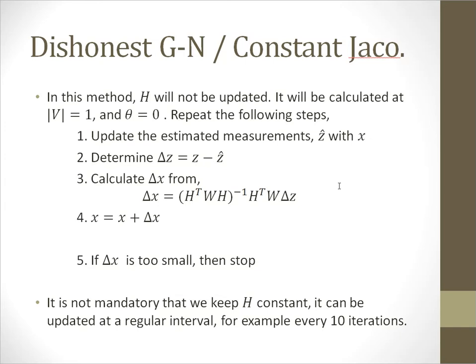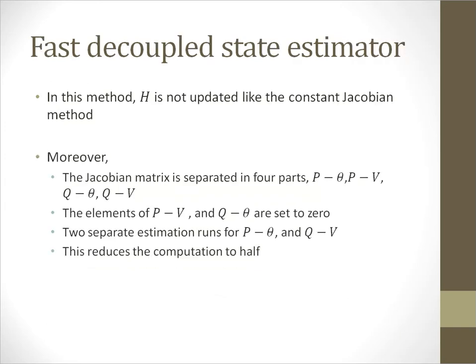In the fast decoupled state estimator, like the constant Jacobian method, H will not be updated. Moreover, we are going to separate the whole Jacobian matrix in four parts: P-theta, P-V, Q-theta, and Q-V. The elements of P-V and Q-theta are set to zero.